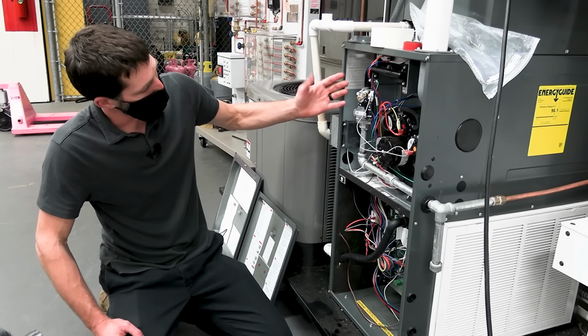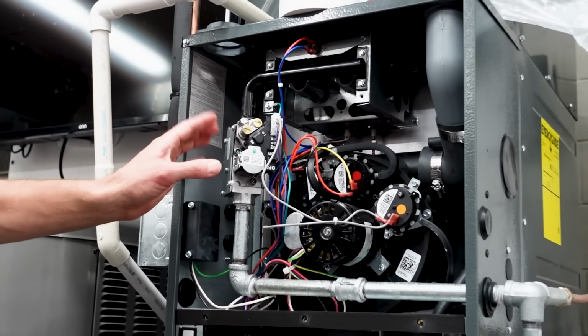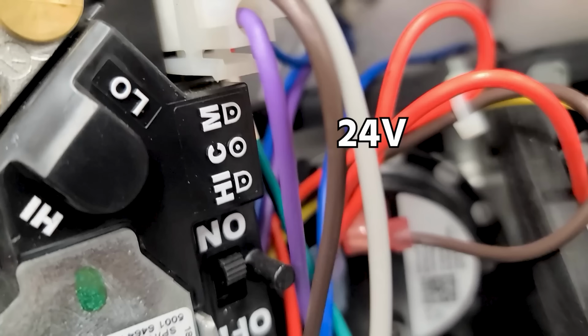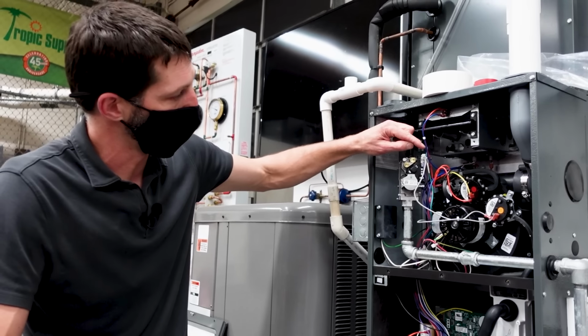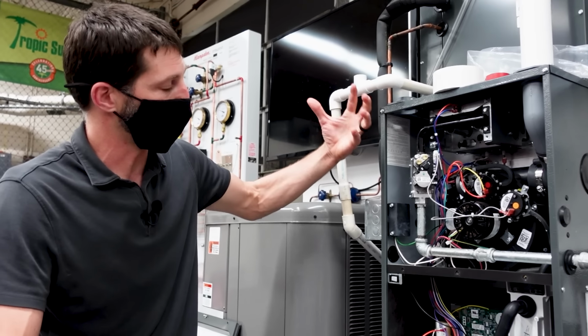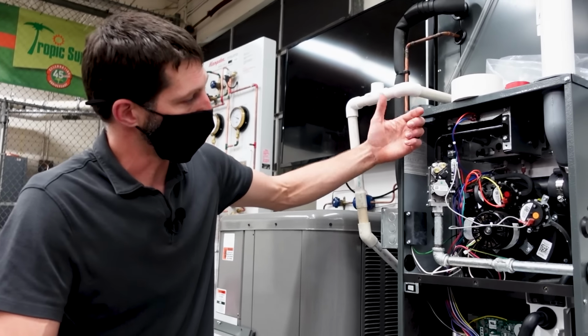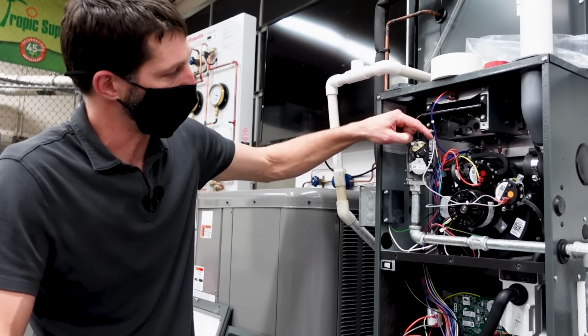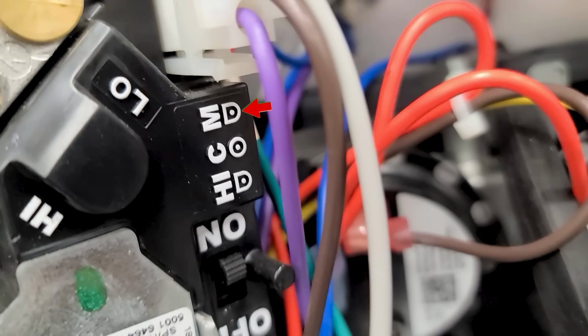I believe on this particular model gas valve, you're going to get 24 volts between common and high with a multimeter if it's running in high speed. You're also going to get 24 volts when you read it with a multimeter, 1 probe in the medium speed and 1 in the common. So both, I believe on this particular one, you have to have both the medium and the high powered to be in high speed. For medium speed or just a single speed, low speed, you're just going to have power on the M right there.